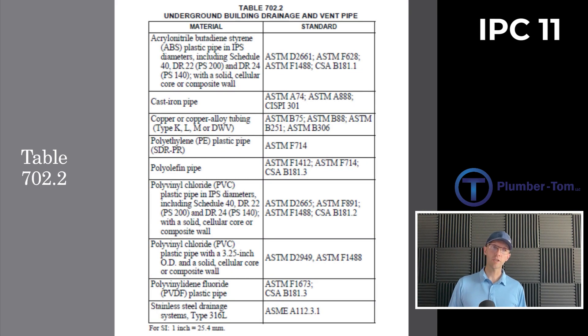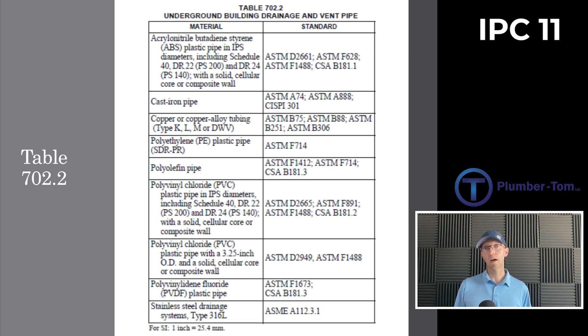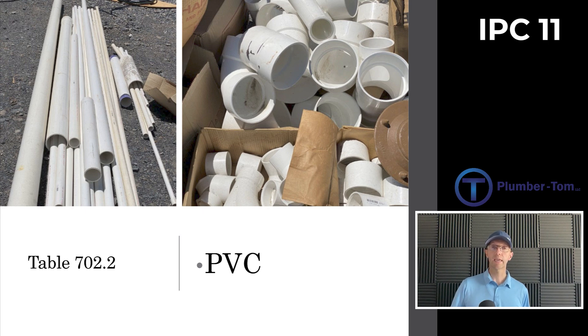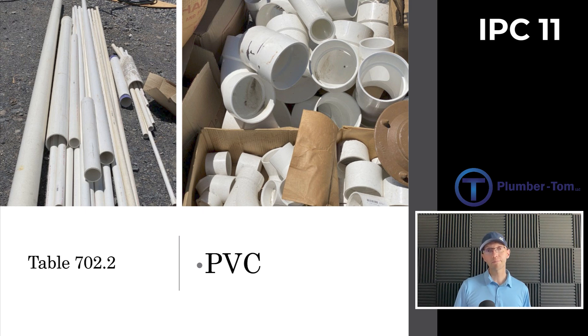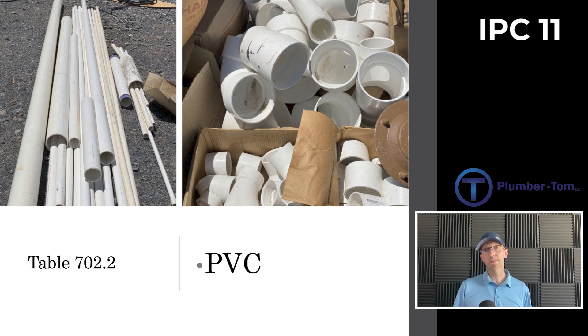Table 702.2 gives us materials that can be used underground for both sanitary drainage and storm drains — a similar list of materials. However, it is not uncommon for storm drains to be run below ground in PVC, because plastics last longer below ground than cast iron. Cast iron has protective coatings, but over time the earth and water eat through, while plastics do just fine underground. Plus, you can't hear it underground anyway, so PVC below ground for storm drainage is very common.